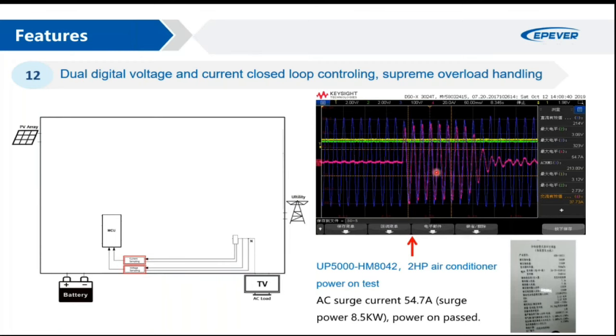But we also do not have a continuous rush current on the circuitry. So this is a trick. We're trying to keep it limited. This way, we can handle the current demand, keep the device on, and successfully pass the rush current demand phase for such a huge load, which is 8.5 kilowatt AC consumer. This is thanks to the closed loop control of the output voltage and current.